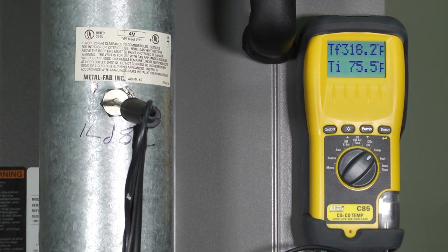What we call that is flame quenching. And that's a huge way of producing carbon monoxide that I can't even really see. It's just quenching the flame enough that I'm not getting proper combustion. And yet I, as a technician or an installer, don't see that. I come back a year from now and I see all the carbon or all the aldehydes or everything else that's on the vestibule plate, but I don't see that when I'm there. With my flue gas analyzer, I'm going to see that right away. So I want to make sure we understand all those wonderful things that we see on it.